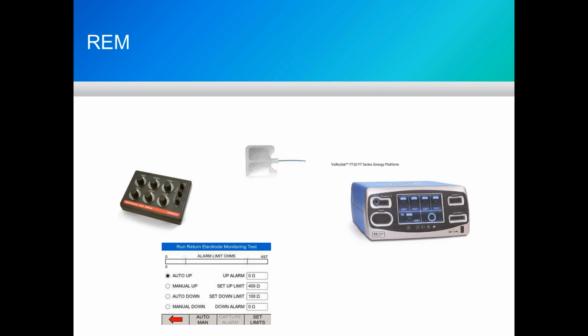But the test process is going to be universal for a number of different analyzers, quite frankly. And the other thing that I'd like to share with you is that the test process is going to be very similar from generator to generator to generator. So the connections that we're making to the analyzer, whether it's a Valleylab or whether it's an ERBE or a Conmed or whatever you might have, the test process itself is fairly similar unit to unit. What's going to change is resistance load values and such, but the actual process is going to be fairly consistent.